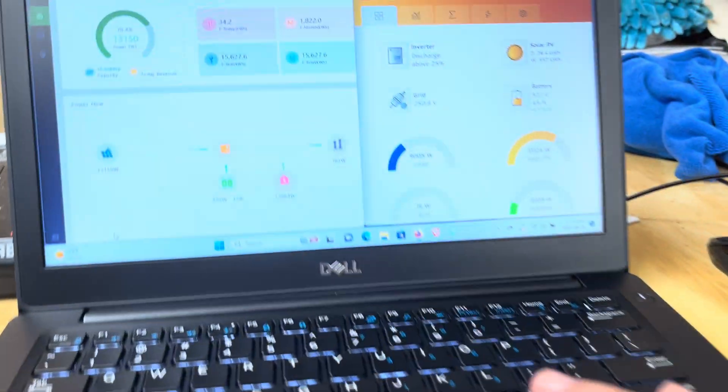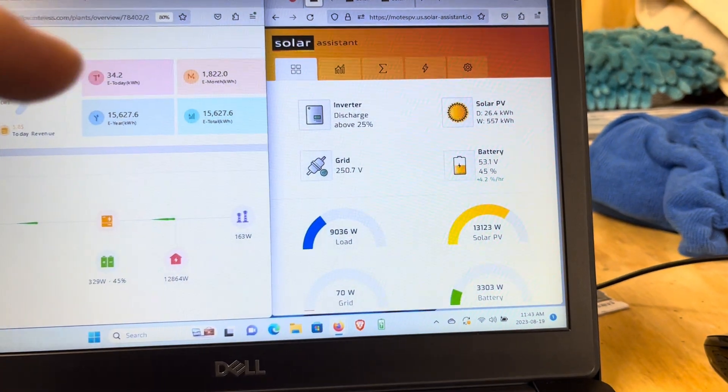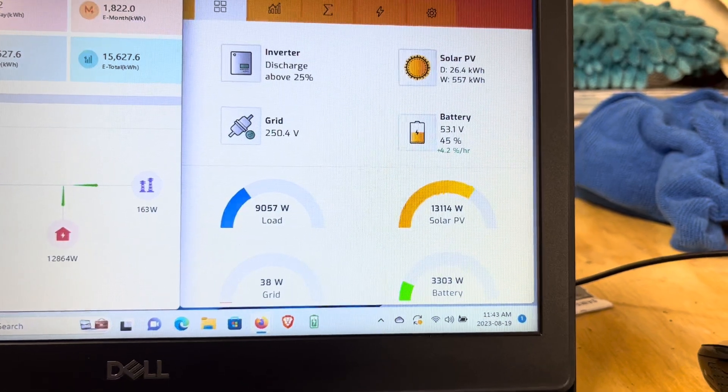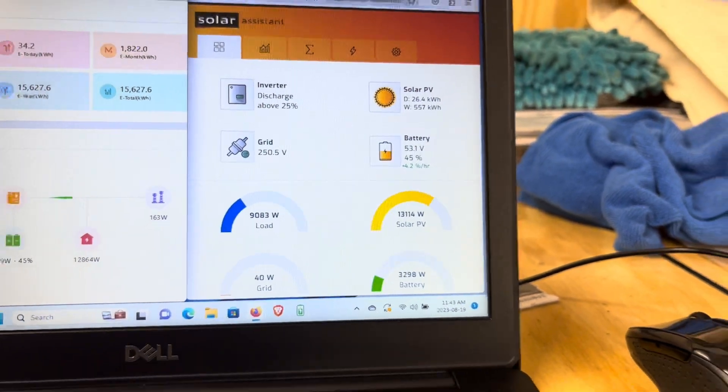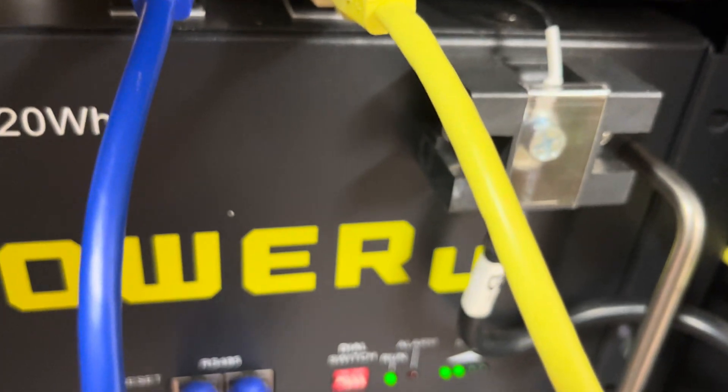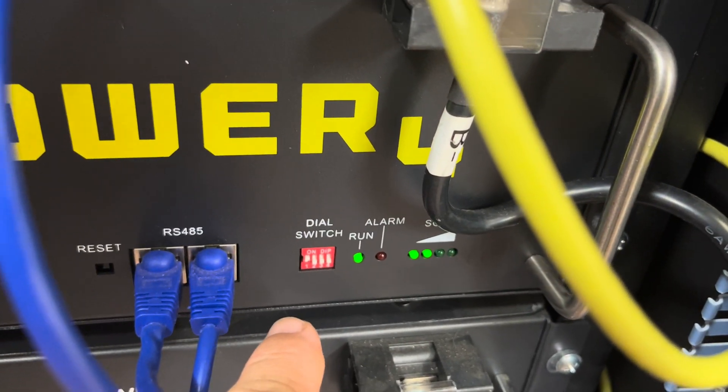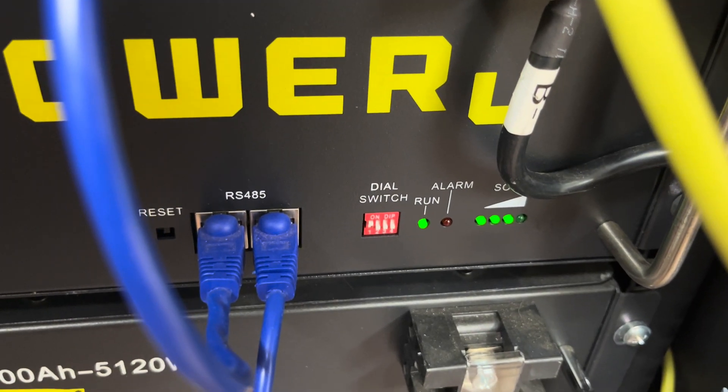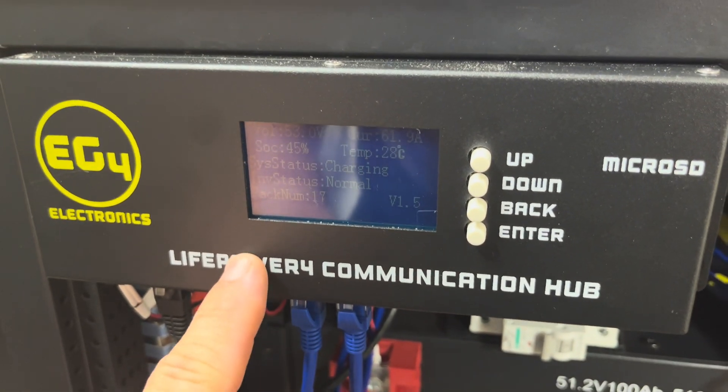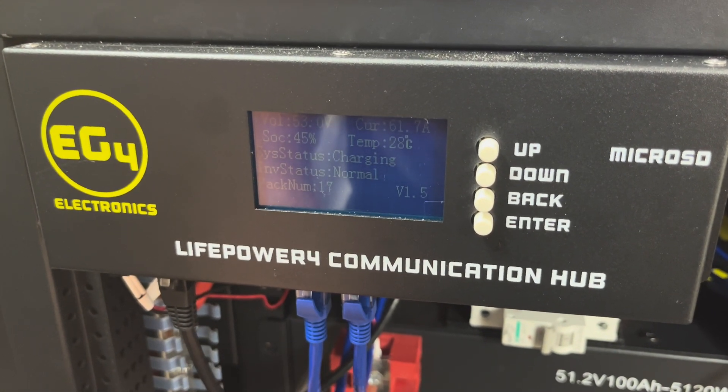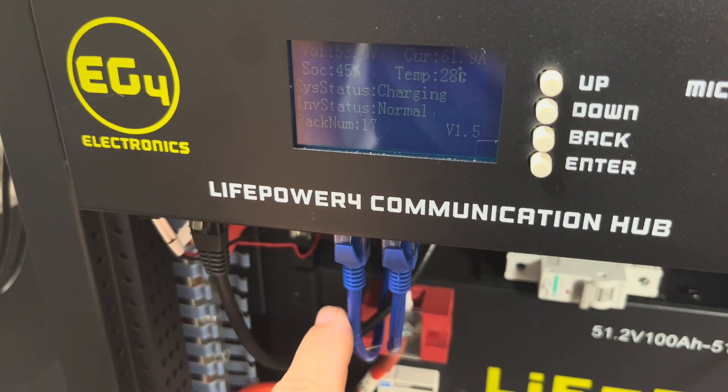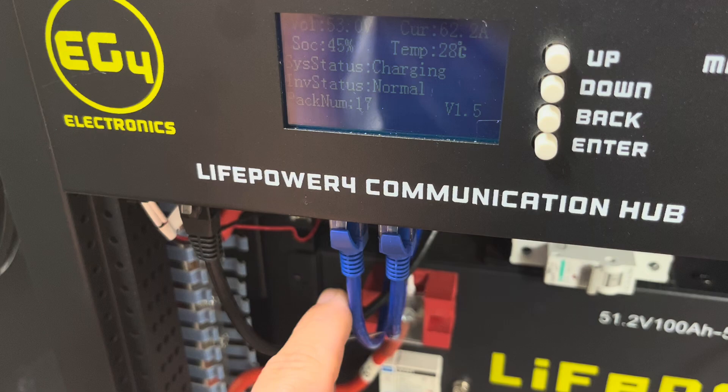The solar assistant will only allow you to communicate with up to 16 batteries at a time. The reason for that is the address blocks here—the DIP switches. There's only 16 unique combinations for a battery address. The LP4 communication hub limits that number of batteries to 15 per port because it doesn't allow you to use address zero.